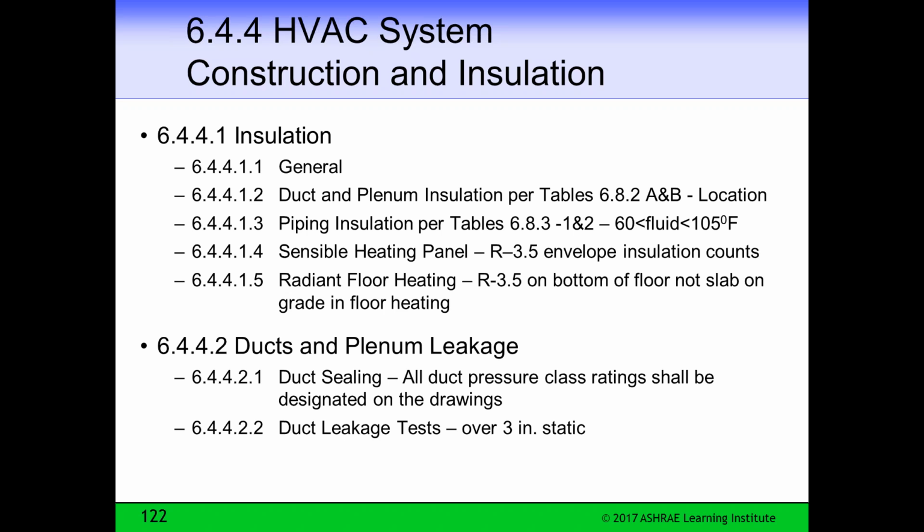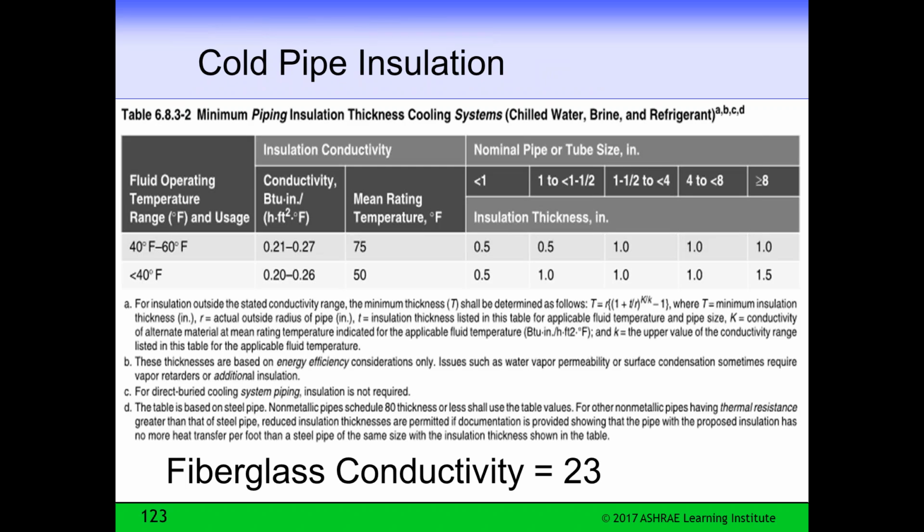And for the duct leakage test, if you put your little symbol on there that you're going to have this length of duct at over 3 inches of static, then you have to test that. You have to have a duct leakage test for those sections of duct over 3 inches of static, and there are requirements in the standard about how much leakage you can have and what percentage of the duct you have to test.